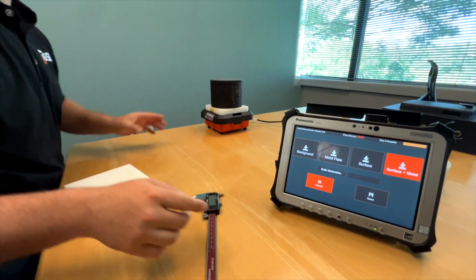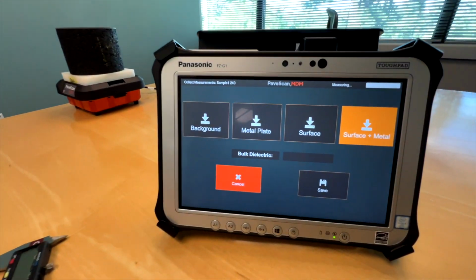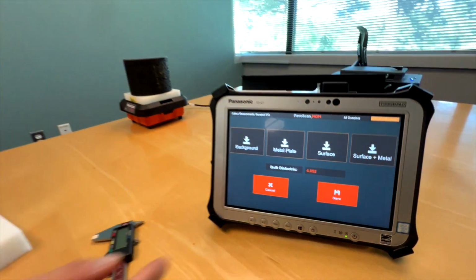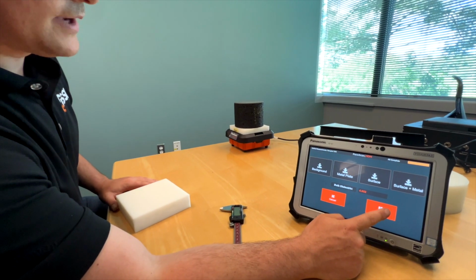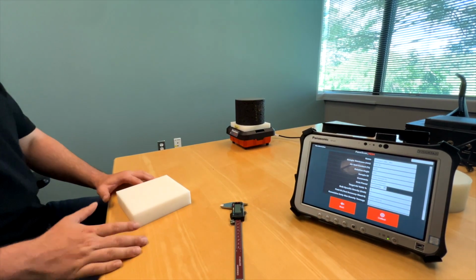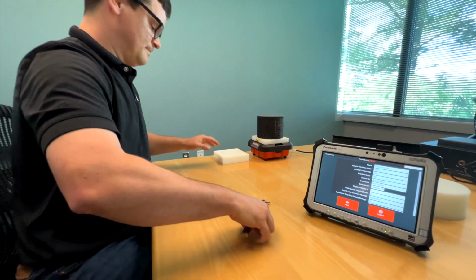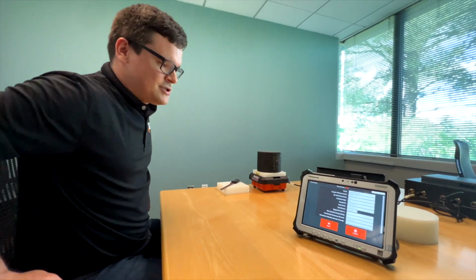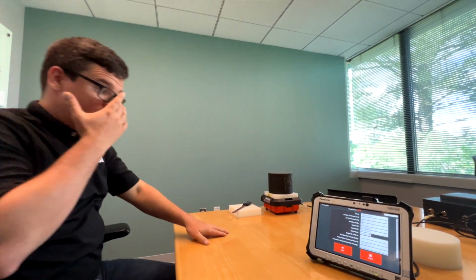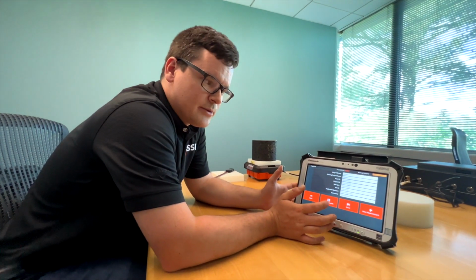Lastly, my metal plate. Okay. It's reading 4.852. Hit save. Now at this point, for this demonstration, that's going to be the end of me measuring these samples. Most likely you would have more samples that you would be using in order to create your correlation curve, so you would have more points along that curve to use. In this case, I'm just going to use this one sample measured 3 times.